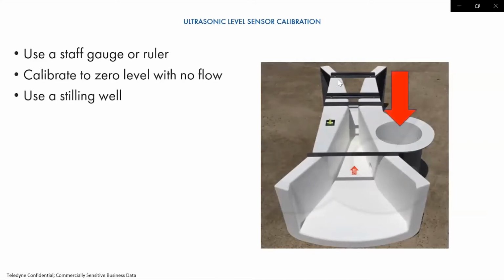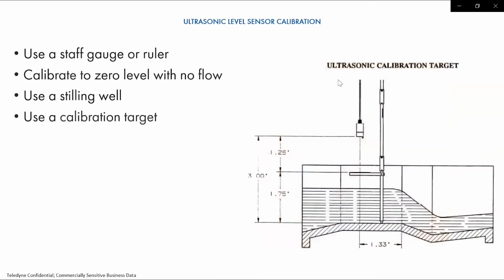If you have the luxury of having a stilling well, what that does, as the name implies, is still the water, so it makes it easy to take your level reading. If you don't have a stilling well, what you can use is a calibration target. This is just a pole with a little platform on it, and you just set that in your flume. If you had this height set to 1 foot, you put it in there, calibrate your level to 1 foot, and remove it. It's a really accurate way to calibrate your level because you have a solid surface. You don't have to worry about the surface of the water.